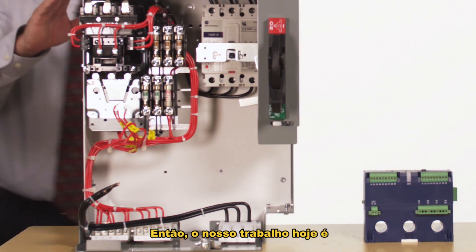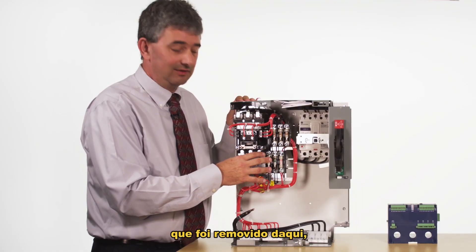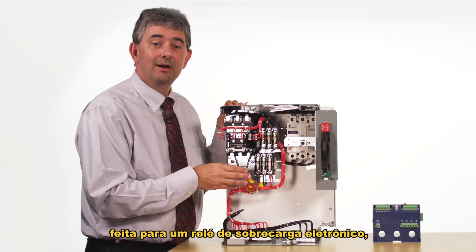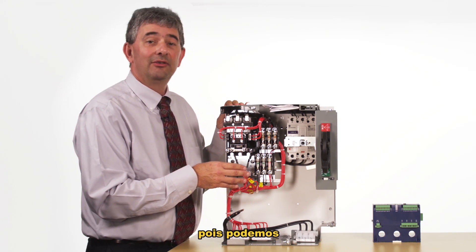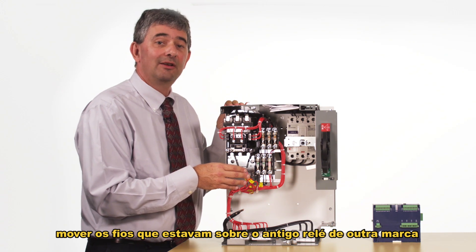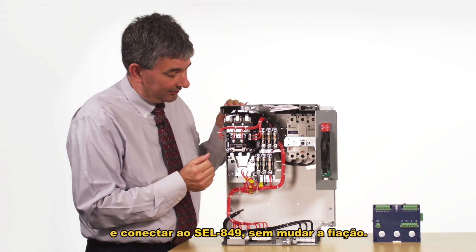Our job today is to replace the electronic overload relay that's been removed here with an SEL-849. Since this was already wired for an electronic overload relay, this is actually a pretty simple task because we are able to move the wires that were on the previous brand X overload relay to the 849 without actually changing the wiring itself.